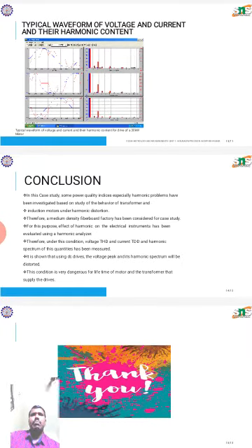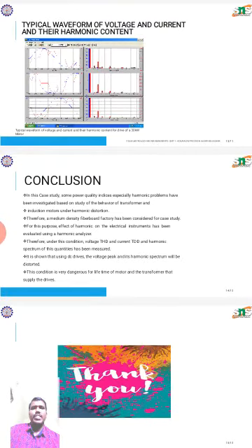Therefore, a medium density fiberboard factory has been considered for the case study. For this purpose, the effect of harmonics on electrical instruments has been evaluated using the harmonic analyzer. Under this condition, voltage THD, current TDD, and the harmonic spectrum of these quantities have been measured.